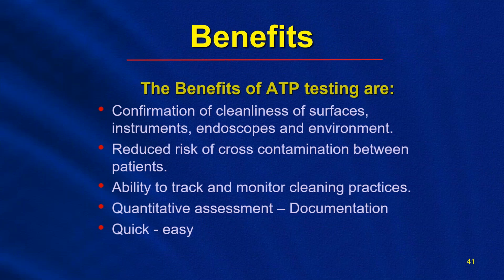It's also a quantitative assessment. You get a digital readout, which can be downloaded from a computer for documentation. If, say, Joint Commission is coming in and they want to know where your documentation is on how you're checking for cleaning effectiveness, you can run reports right from the computer. But the biggest thing is that it's a quick and easy test. You will get results in as little as 15 seconds.